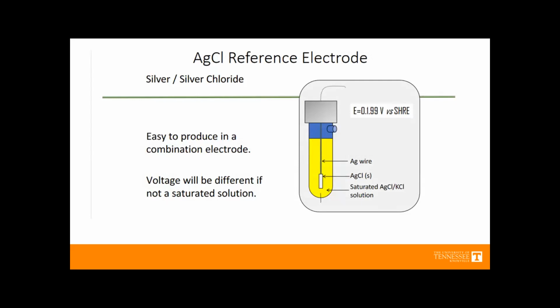All right, so this is an Ag-AgCl reference electrode. The half reaction itself is going to generate about 0.199 volts. So when we make our reading, it's already got 0.199 volts on the reference side, and that'll be nice and stable. The reason it's stable is that in our solution of silver and silver chloride, we're going to have some KCl solution in here. On the surface of this wire, we're going to build up a solid AgCl precipitate.